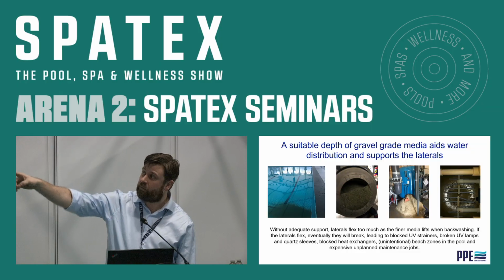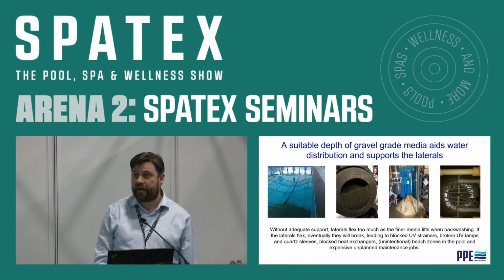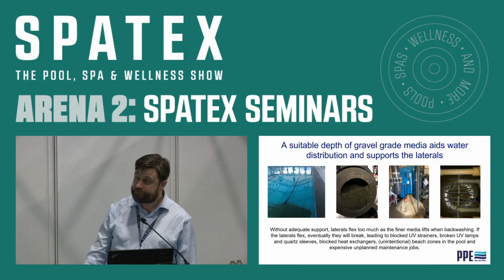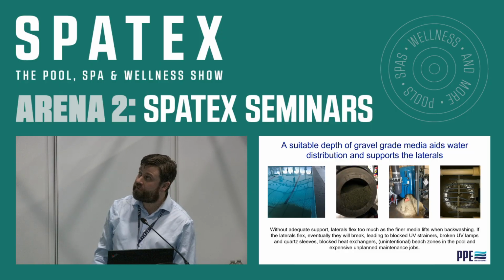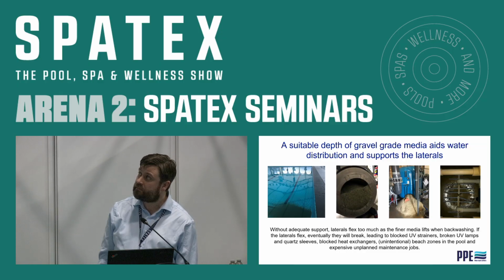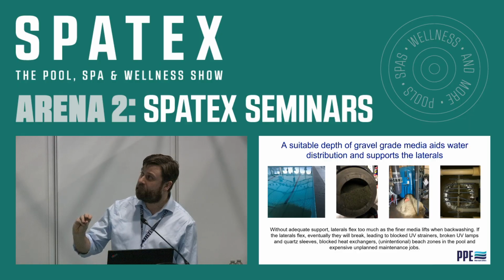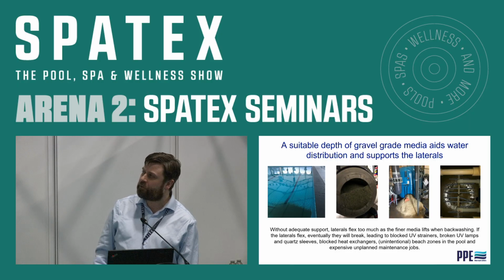The first thing was, okay, flow rate's gone down, heating's not really as it should be, and we had to tell all the customers that we have a new beach zone in the pool. The photo along from that was actually the UV chamber, which got filled with media, and that can be an issue, especially if you do have some issues and you actually wipe out the quartz sleeve and the lamp.